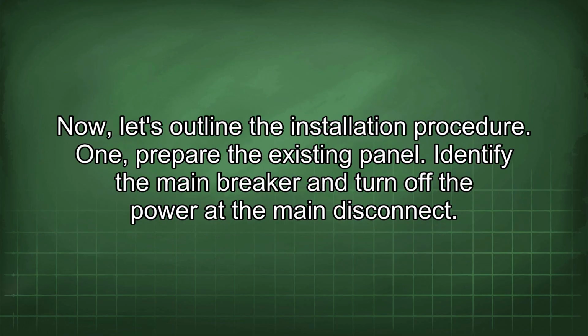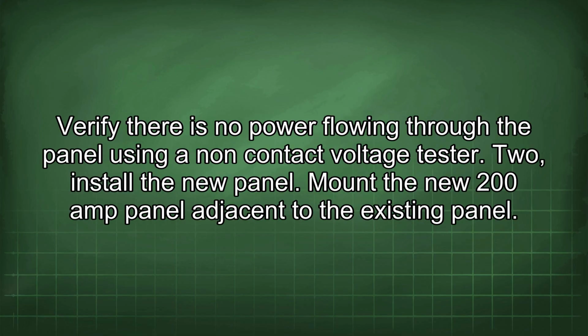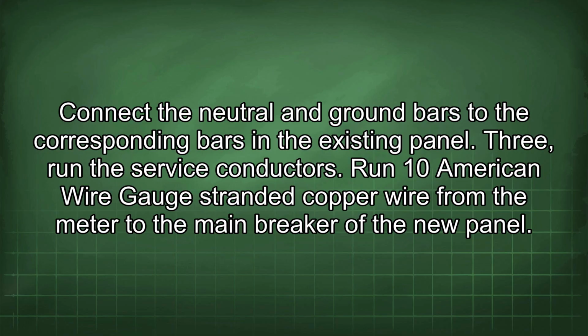Now let's outline the installation procedure. 1. Prepare the existing panel. Identify the main breaker and turn off the power at the main disconnect. Verify there is no power flowing through the panel using a non-contact voltage tester. 2. Install the new panel. Mount the new 200 amp panel adjacent to the existing panel. Connect the neutral and ground bars to the corresponding bars in the existing panel.